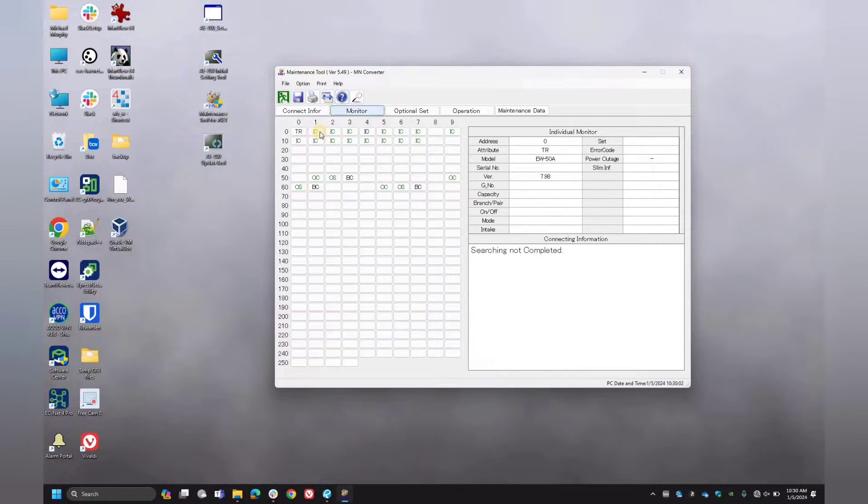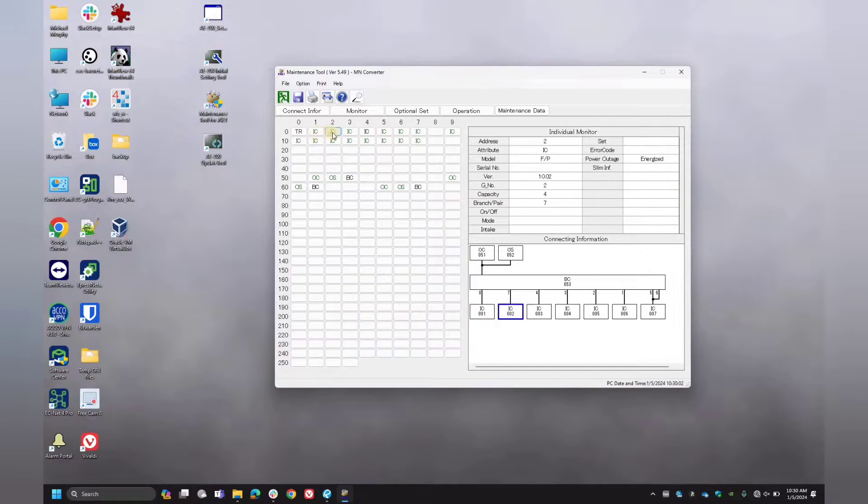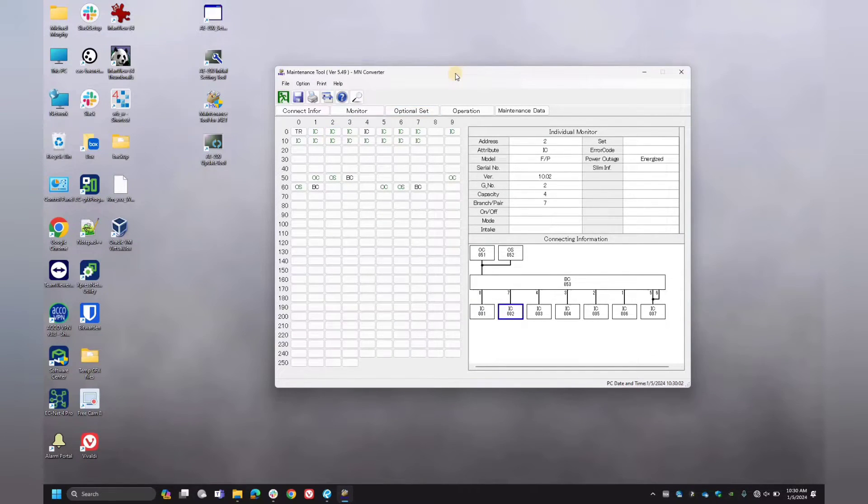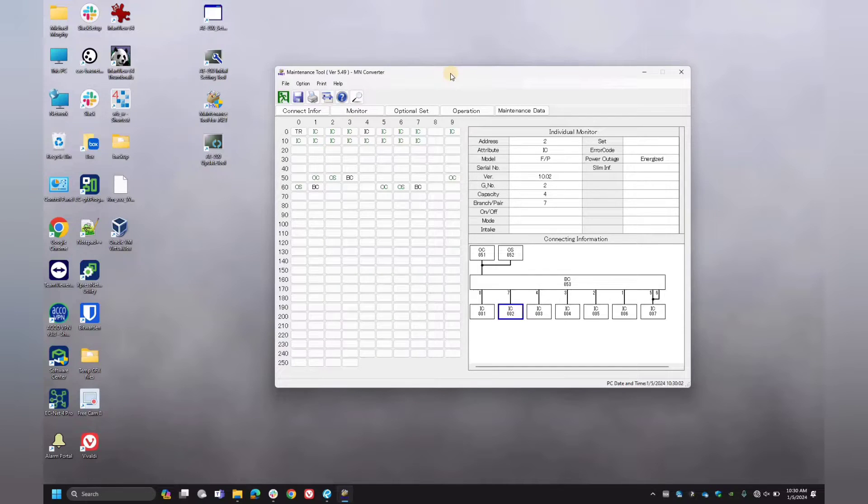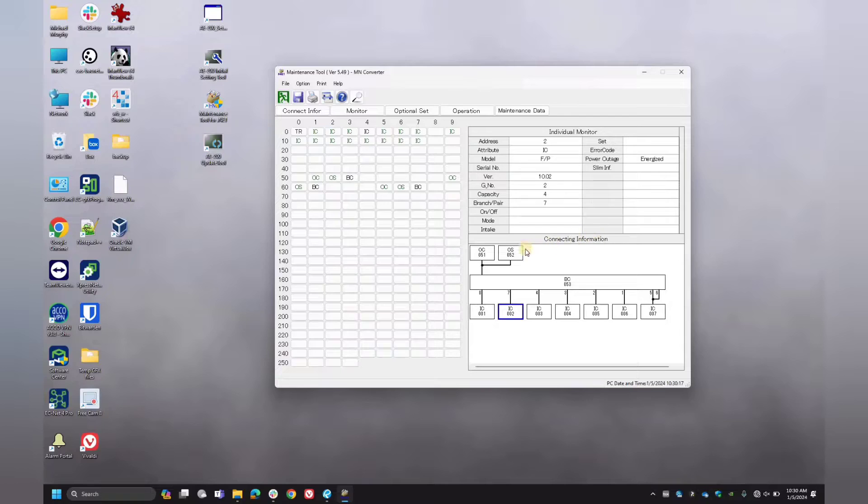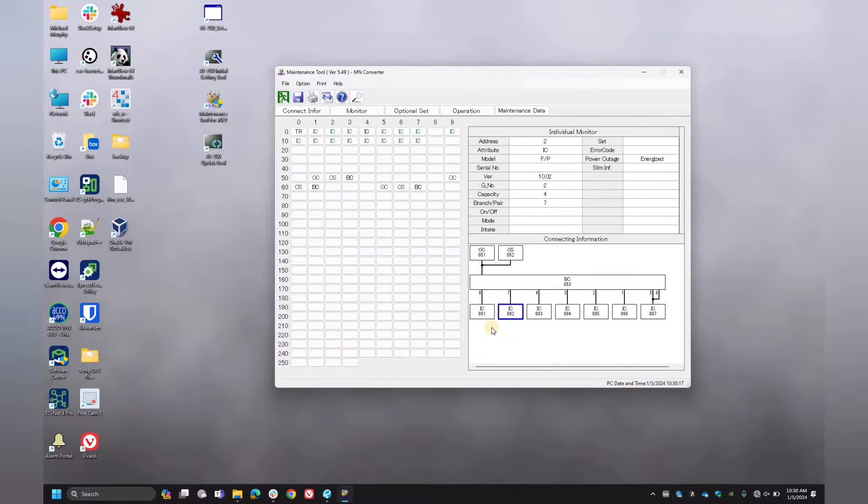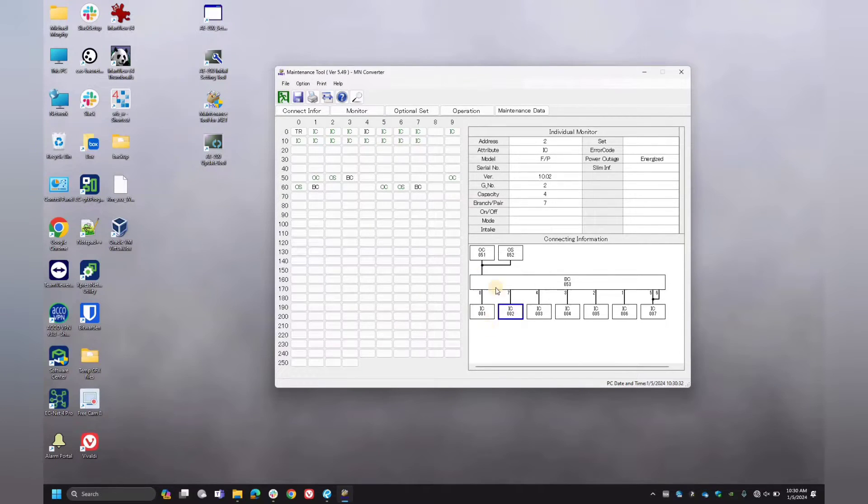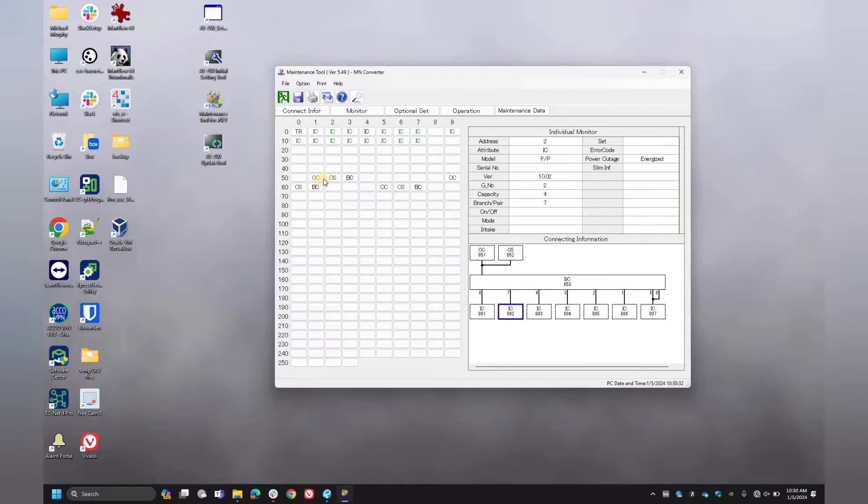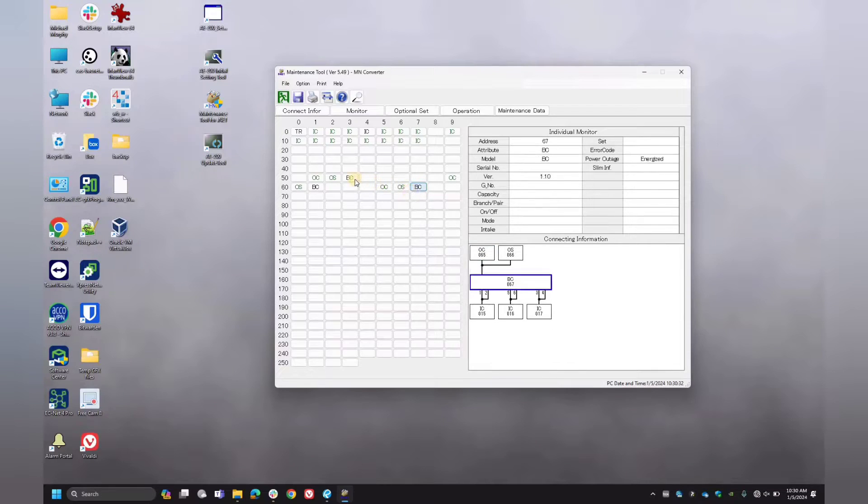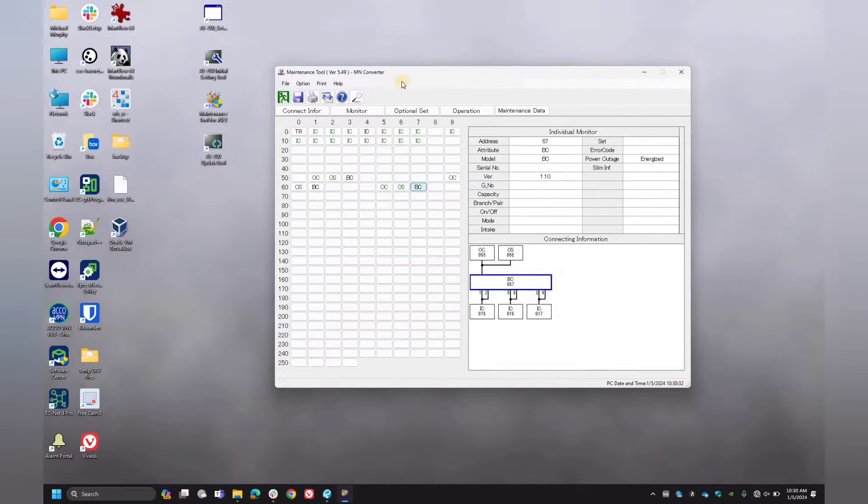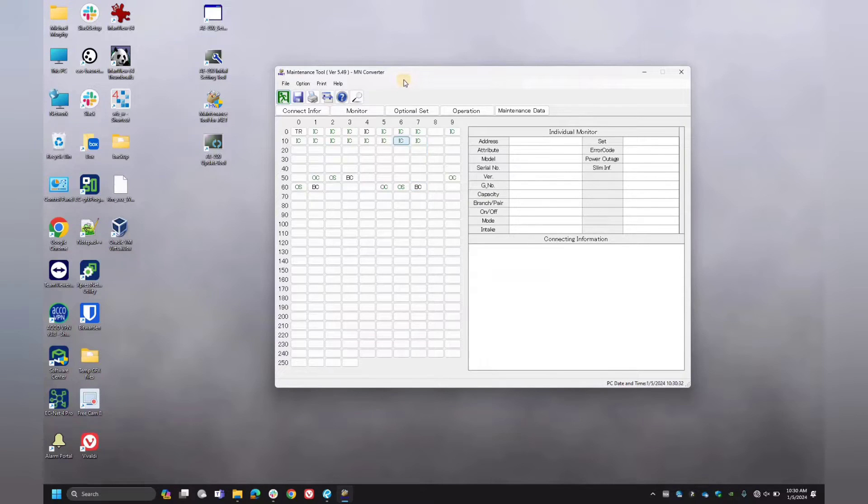Now these other items here, as you can see, which are denoted by the IC abbreviation, this is your actual split system units. So here we're using the VRF units here, and I'll post a picture of it right here. But as you hover these, it'll actually also highlight down below here. This is pretty much like your network riser. So this will show you how all the devices are connected to the central controller. These OC and OS units and the BC units are pretty much like your outdoor condenser units. So that's showing you where these are all connected here.